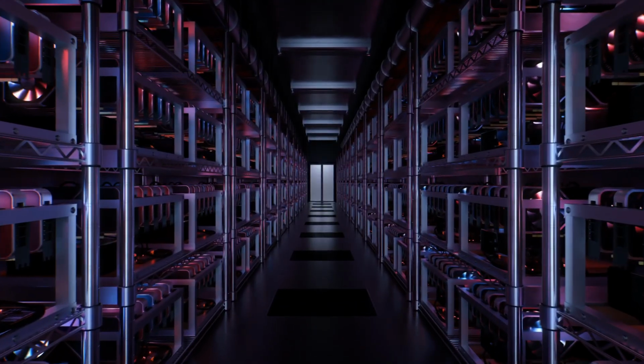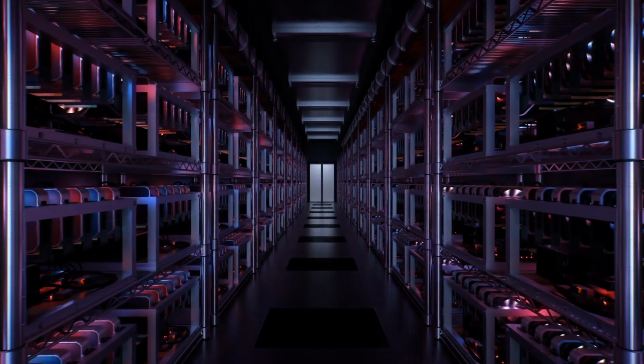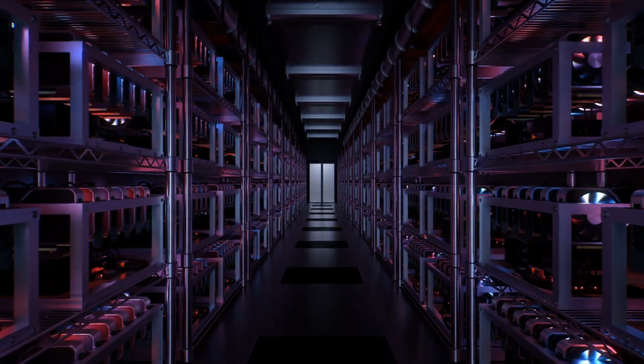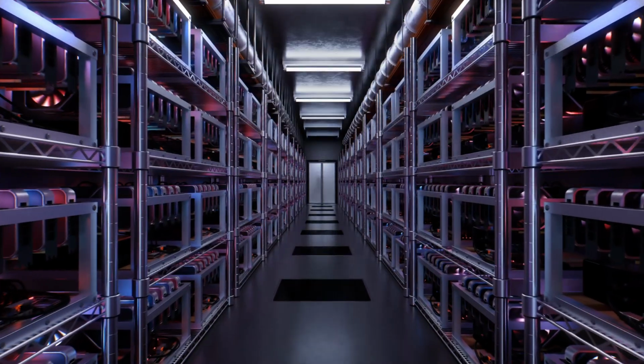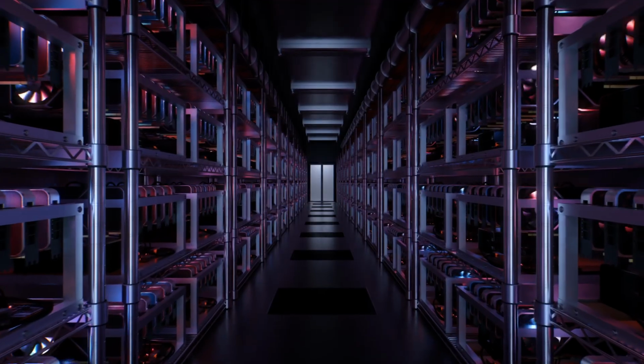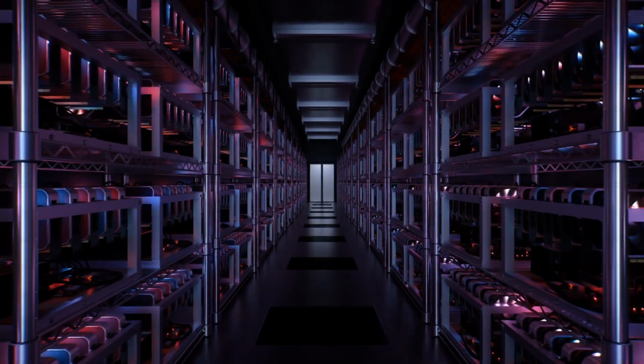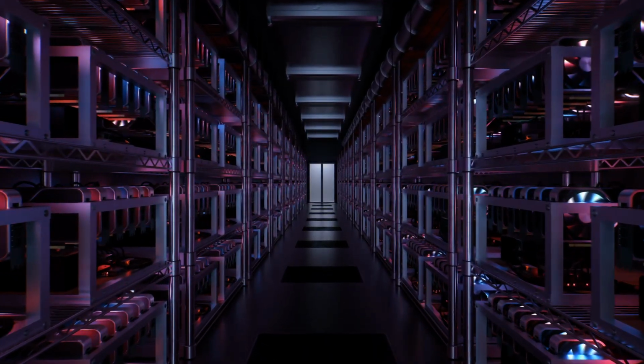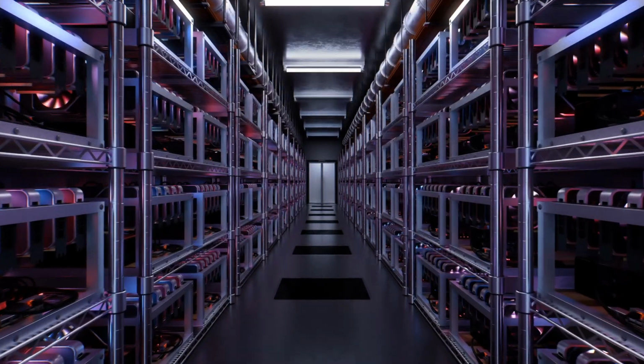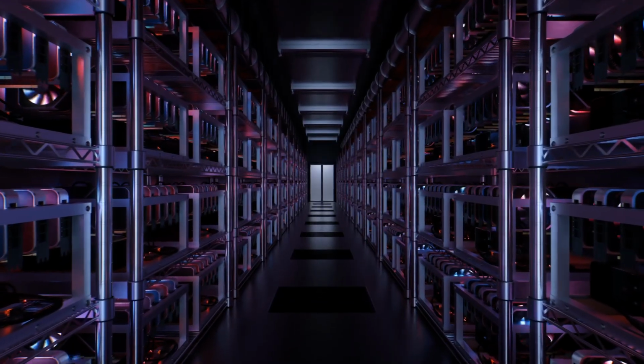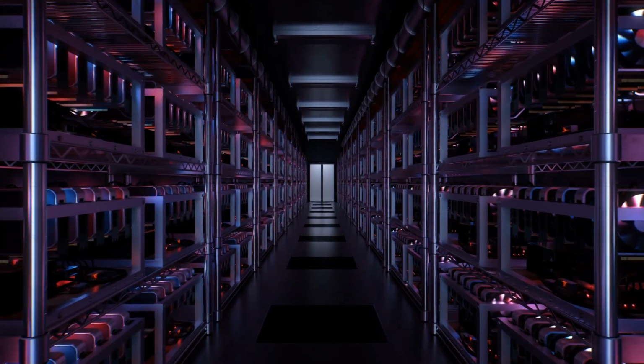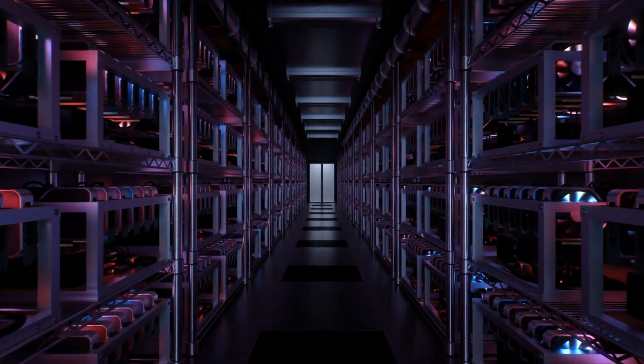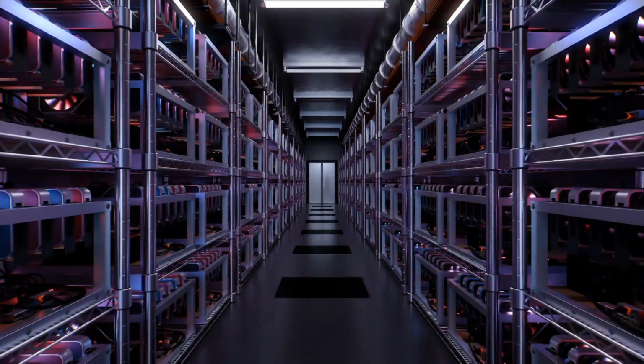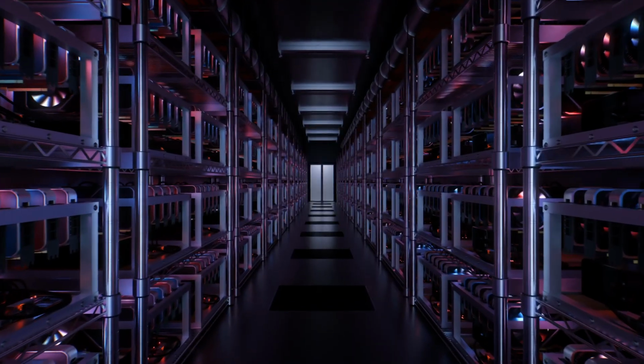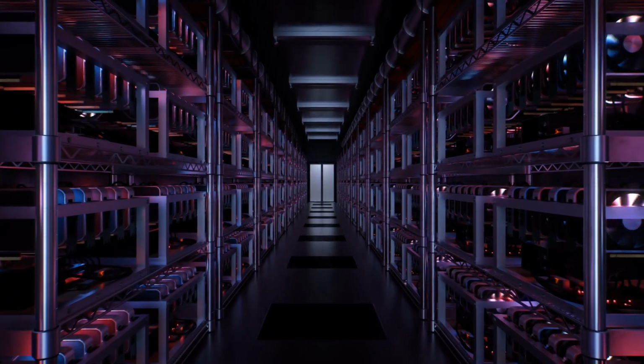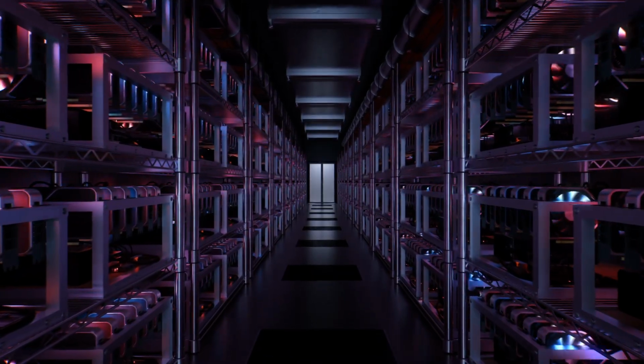Now, contrast that violently high-pressure, somewhat gritty primary loop with the secondary side, which the source calls the IT side. This is the side that matters most to the hardware. Yeah, this is a fluid that actually leaves the CDU, travels into the server racks, and snakes its way through the delicate manifolds that sit directly on top of the GPUs. And this environment is strictly controlled. Completely different rules apply here. First, it doesn't use massive volumes of water. The system holds exactly 100 liters of a very specific fluid, propylene glycol, at a 25% weight concentration.